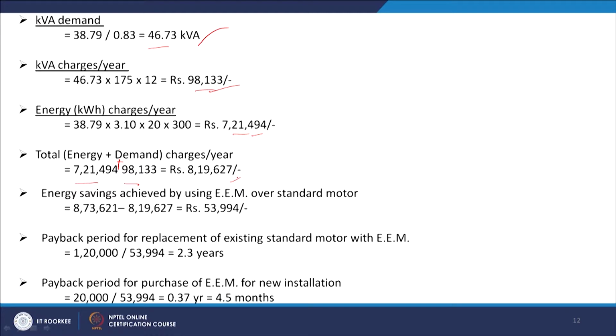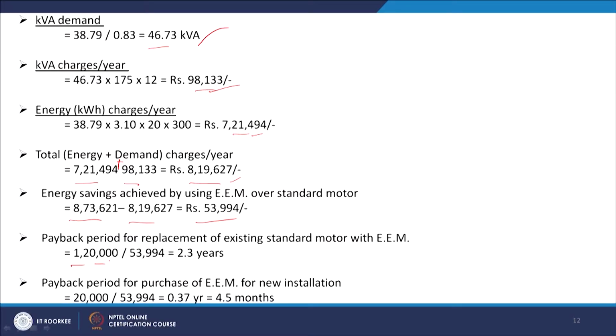So, here we are getting this much in the standard. If we use the standard motor, our charge is 8,73,621, and here 8,19,627. So, the difference is 53,994 rupees. So, this is our saving actually. So, for the payback period, if I want to get the whole money back, that is 1,20,000 for the energy efficient motor, then we have to divide this by 53,994. So, it is 2.3 years.